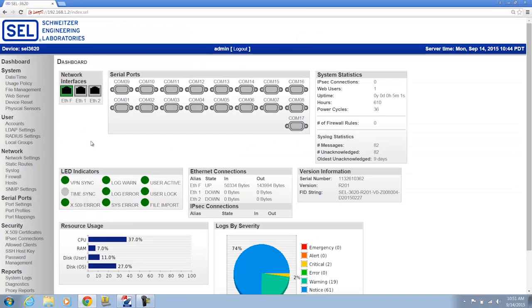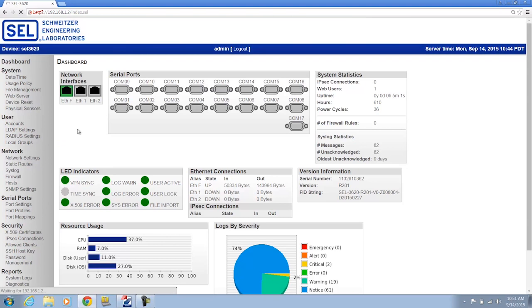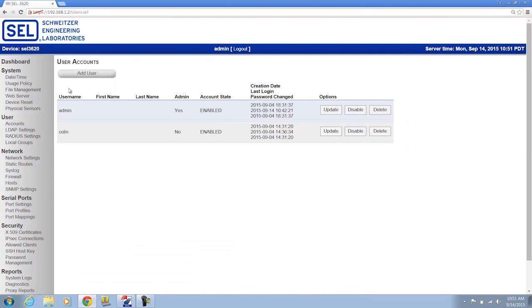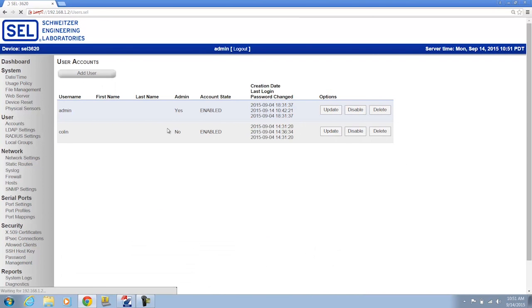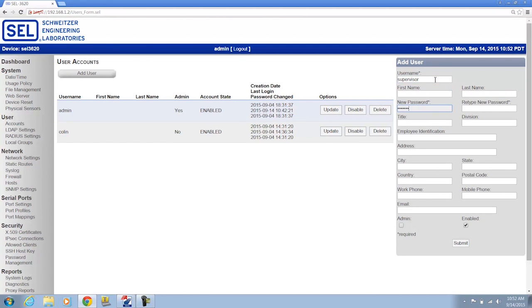First of all on the SEL 3620 interface I'm going to go to Accounts and I'm going to go ahead and add a supervisor account. That supervisor account is going to have supervisor privileges to the relays on my SEL 3620.